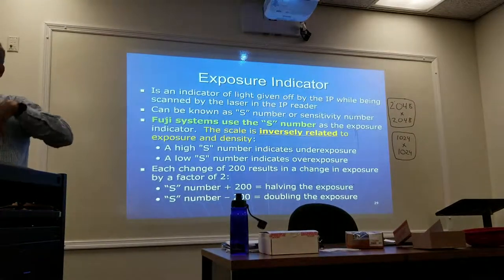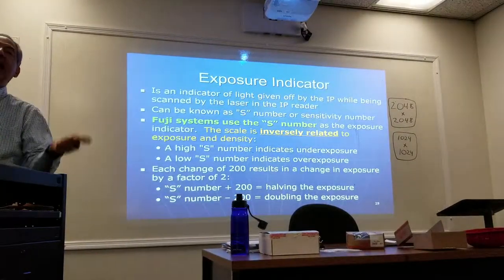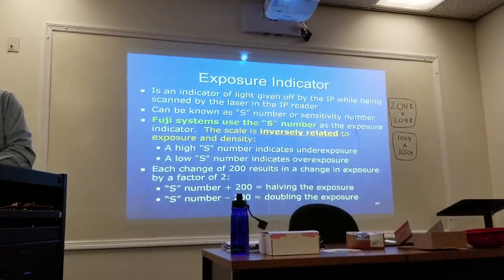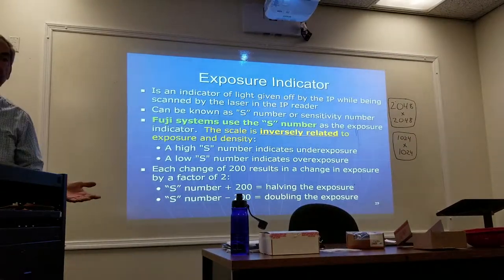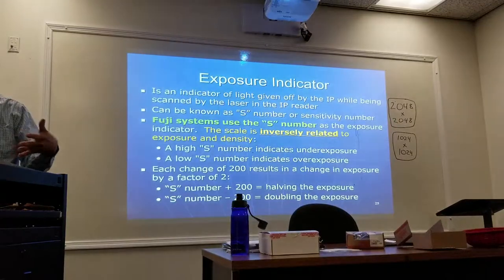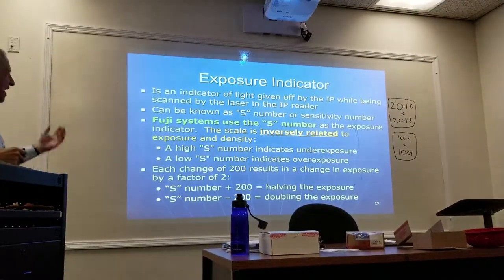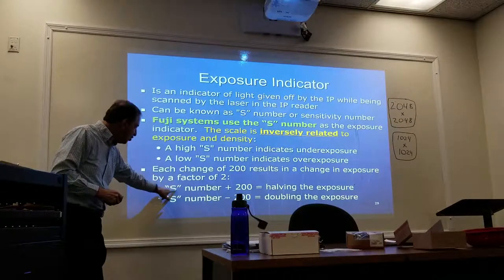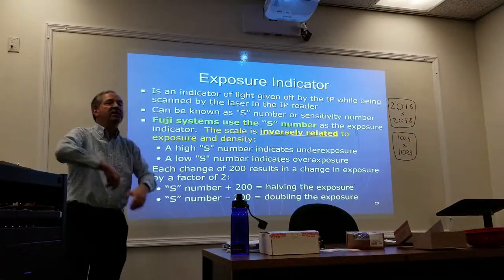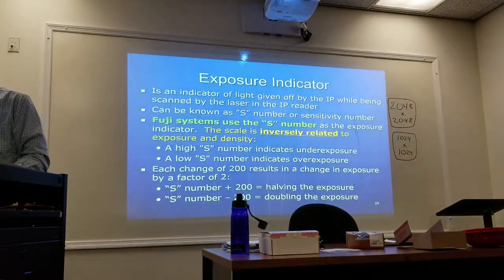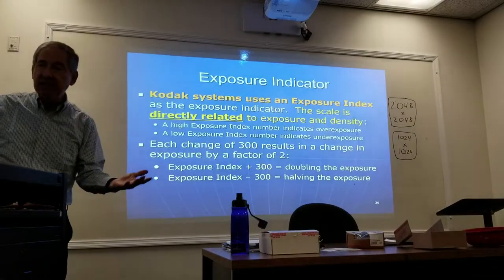For exposure indicators: Fuji uses the S-number, and the scale is inversely related to exposure density. A high S-number represents underexposure; a low S-number indicates overexposure. When you change the S-number by 200, it changes the exposure by a factor of two — adding 200 cuts the exposure in half, subtracting 200 doubles it.